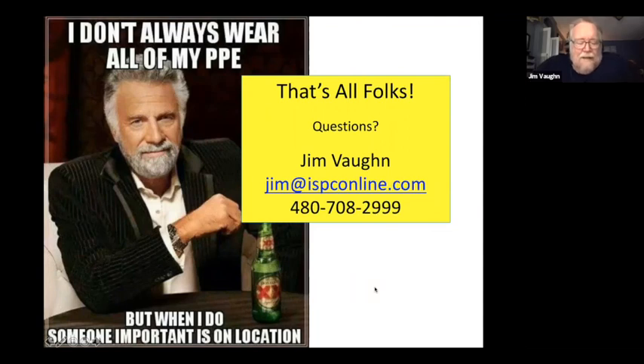Now, we'll tell you this. The guy that wrote these tables, we were actually across from each other in a litigation. He represented OSHA, I represented a contractor, and we were just shooting the breeze. And I said, hey, what's the deal with TOV of 3 in the alternative table? And he says, well, frankly, we put it there to encourage people to actually calculate, because typically TOVs are going to be 1.5, 1.7, 1.82, somewhere around there. He says we didn't think that anybody would ever think that they were going to have to work at a TOV of 3. So it was put up there in order to compel compliance. But the way that we work, back to the answer to your question, if we work single phase to ground, our MAD calculation with TOV is phase to ground.